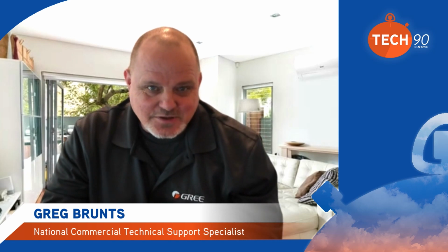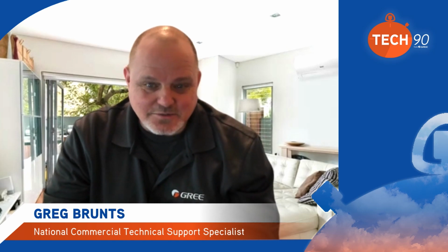JD and I did a training on the mini splits where we put a rheostat on there and played around with the temp, adjusted the rheostat and adjusted the resistance. And yeah, we could make that machine fault out no problem. Right, JD? Oh yeah, that was fun. So, just take your time and think about what you're doing and you'll be able to get to the bottom of the problem. So with that, let's move on to some of these questions.